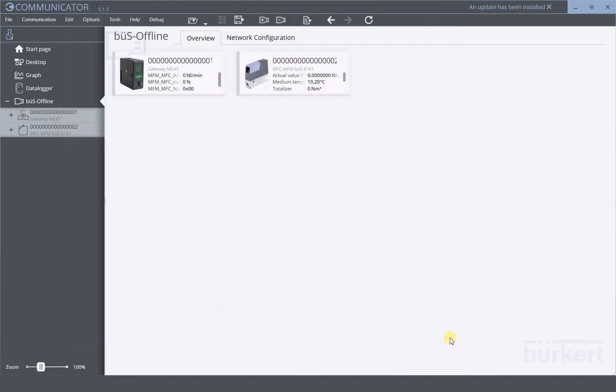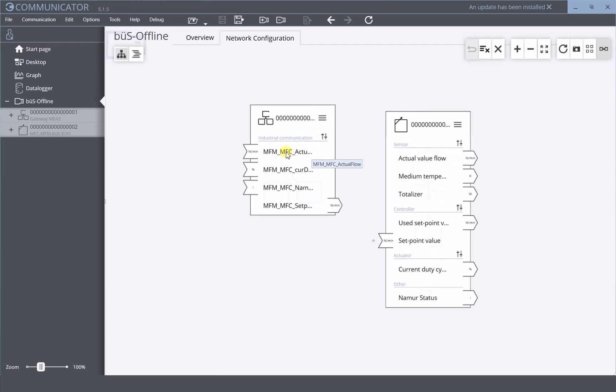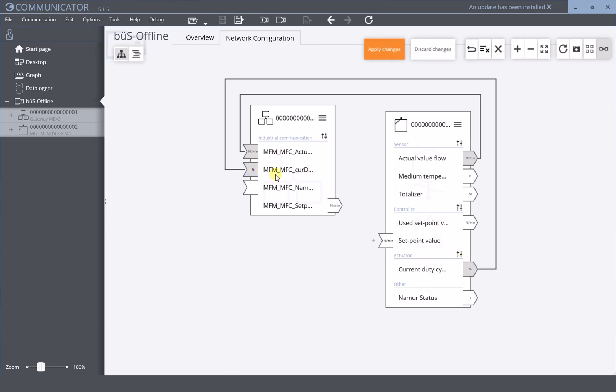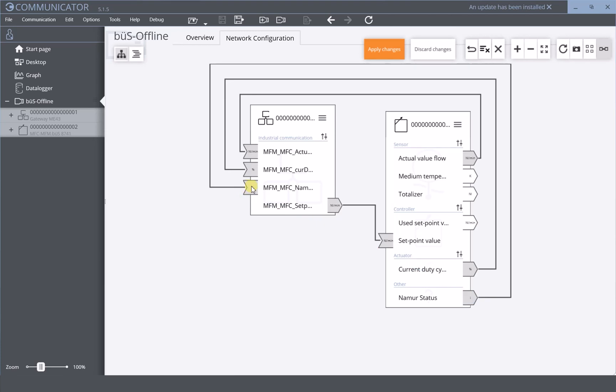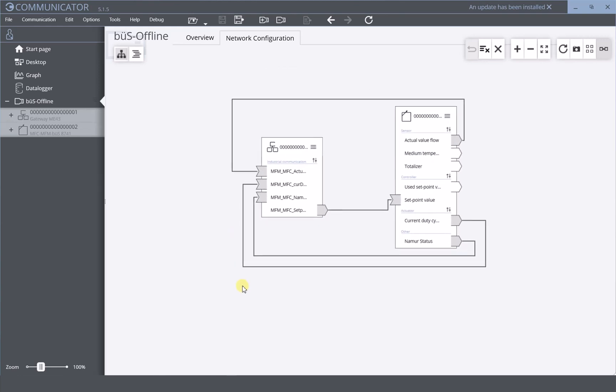Now let's proceed to the last step of the configuration, which is the mapping between the gateway and the field devices — in this case, the MFC. For this, select the tab network configuration. Now we have the gateway and the MFC right next to each other. The mapping can be done by simply creating lines between the right values. The actual flow can be connected to the actual flow of the gateway. The current duty cycle in this manner. The setpoint value can be assigned, and the Namur status as a feedback from the device. Once these connections have been made, apply changes so that the gateway can load this configuration and restart. All these connections have been accepted by the gateway and have been read into it.